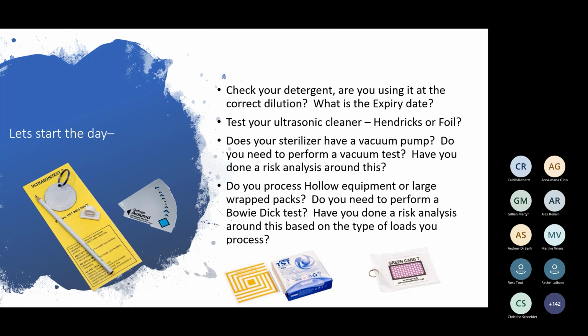And then after the 6 minutes that you've run it, you pull the pencil out. You make sure that all the shaded pencil that you've put on the disc has lifted and is gone. And then once you do that, the device is ready for the day. Much, much easier, much cheaper, and much quicker to do to test your ultrasonic.